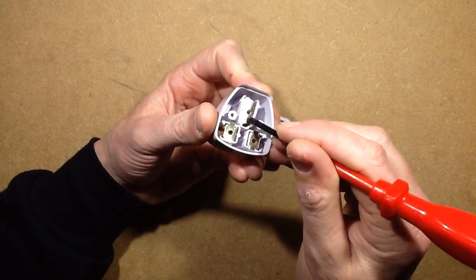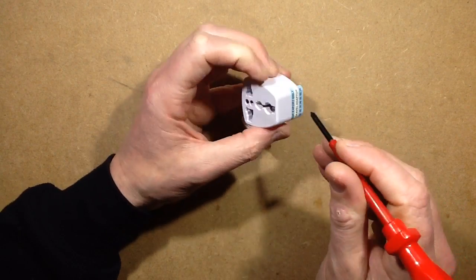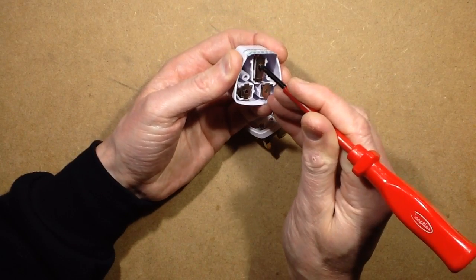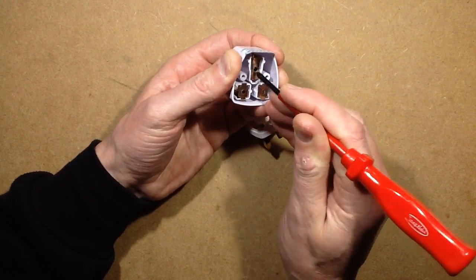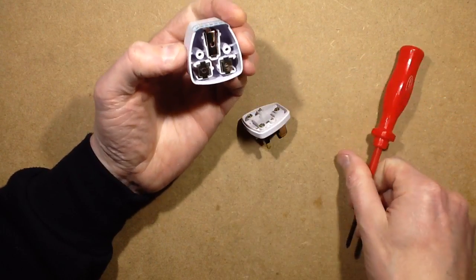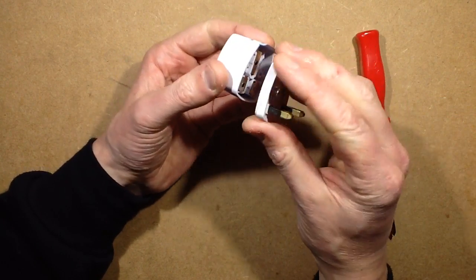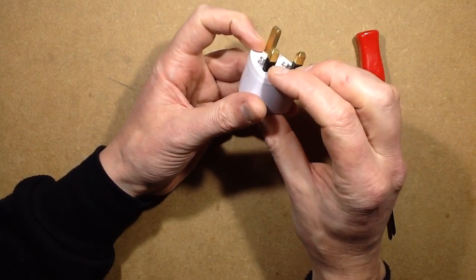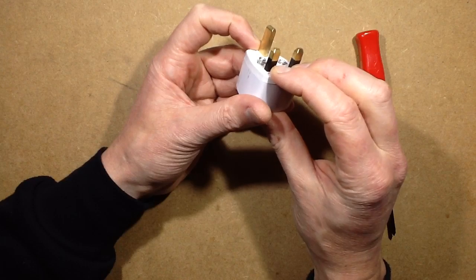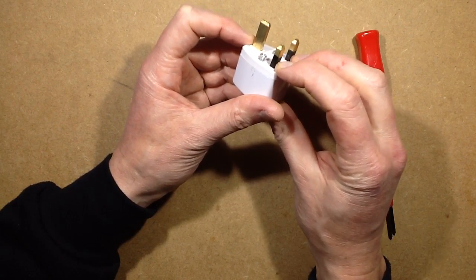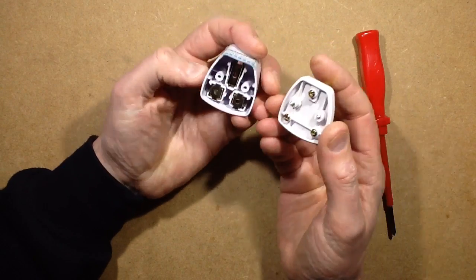And the earth actually looks as though it's sticking down further than the others, so that's why it's not making contact because it's actually further away than the others. I wonder if it even makes decent contact with those ones. It was making continuity, but it's just barely because there's just the tiniest bit - it closes up almost completely before it actually makes connection. They're horrific, they're worse than I even remember seeing before.